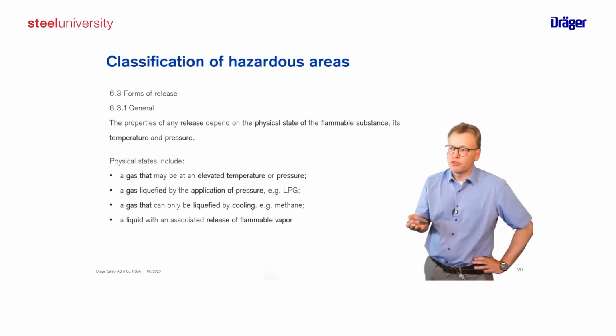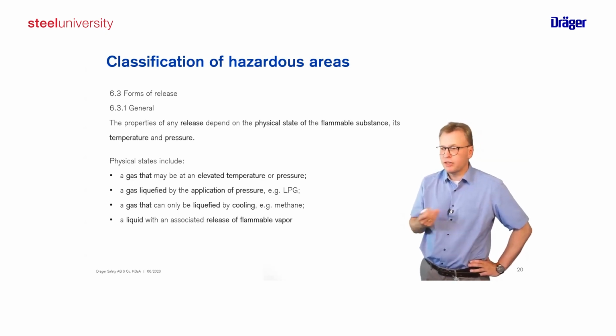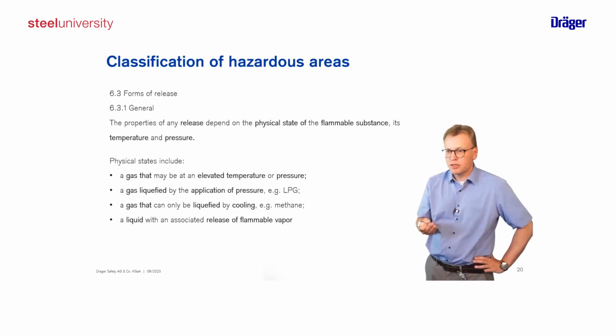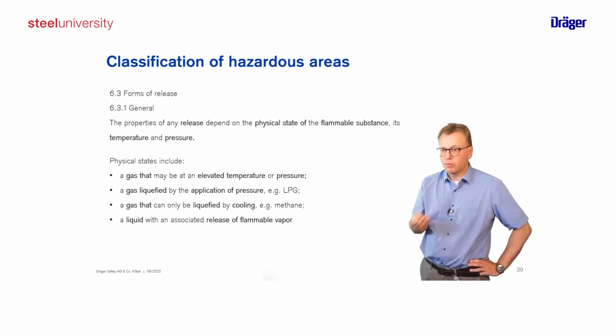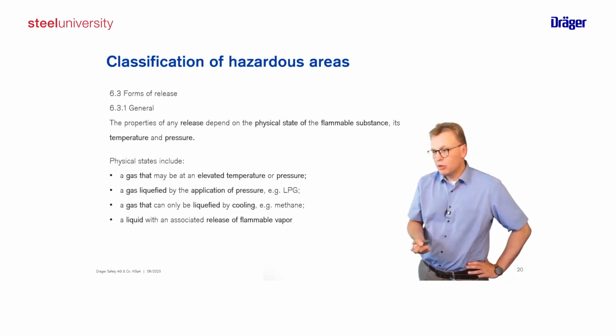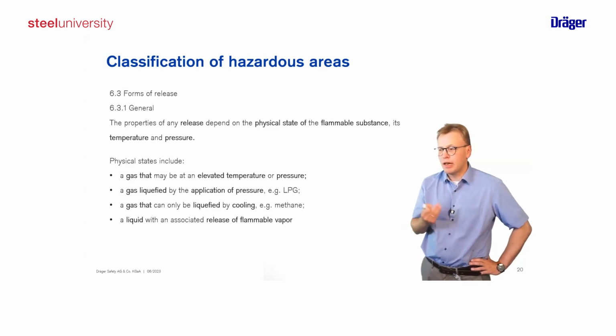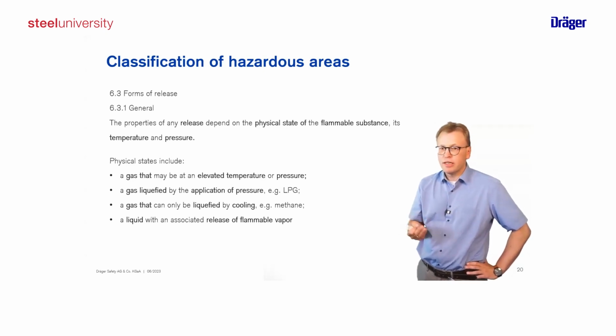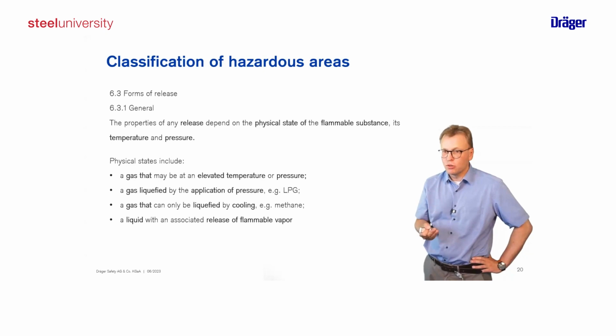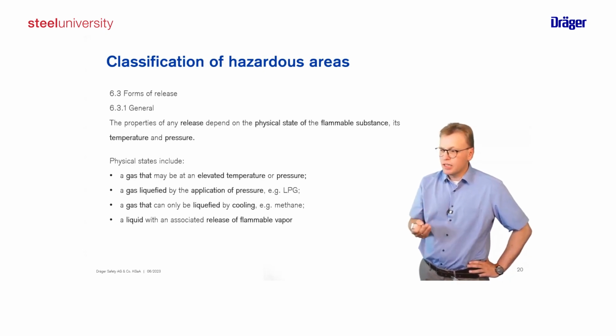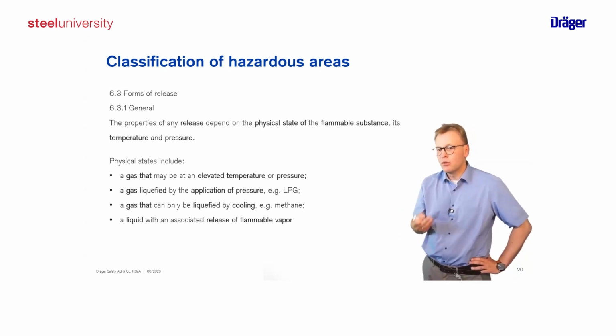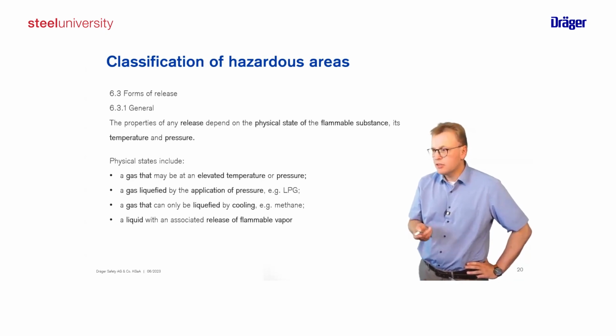is we need to consider the forms of the release, as hydrogen can be in different physical states. It could be a gas, it could be compressed, it could be a liquid. So if we speak, for example, about electrolyzers, then when this is leaking, depending on whether it's a normal pressure, it could be just hydrogen as a liquid leaking out and then vaporizing. If you have a high pressure electrolyzer, it will be compressed gas. So you will have different forms of release of your hydrogen, and this needs to be considered in your measures.